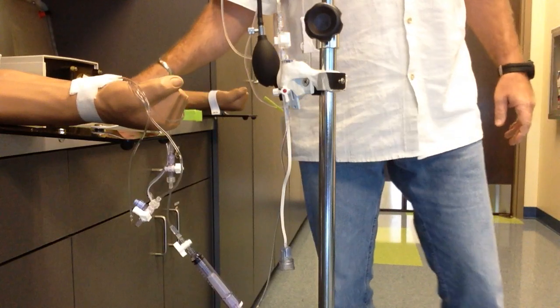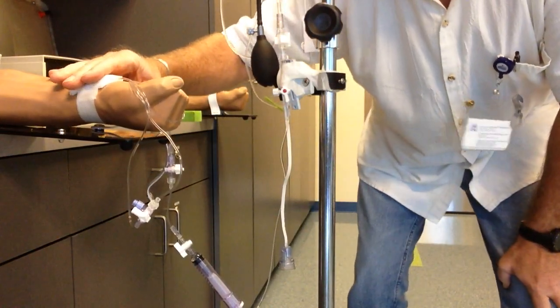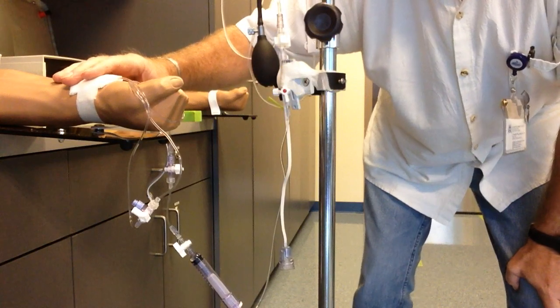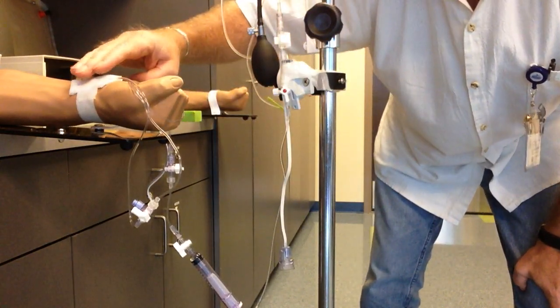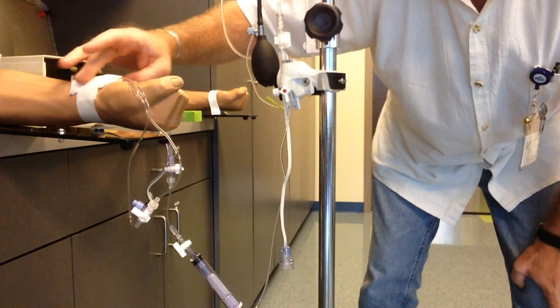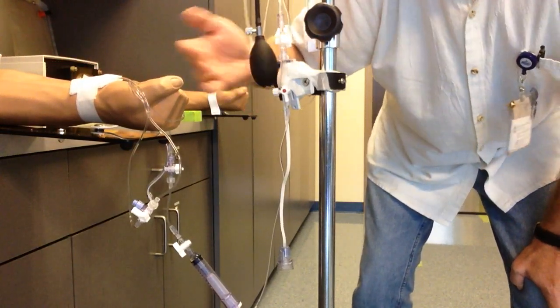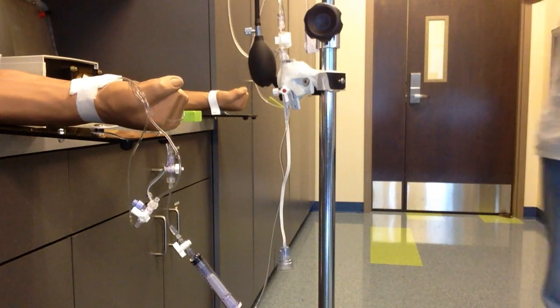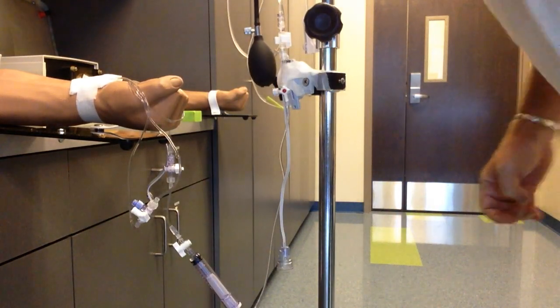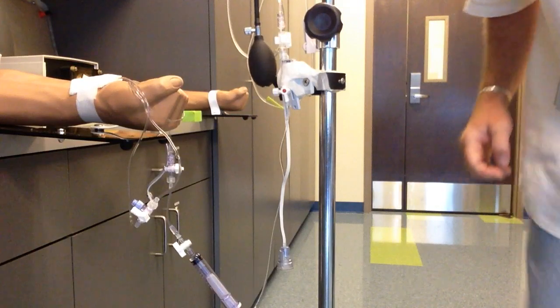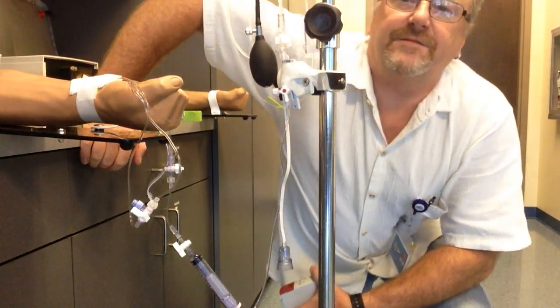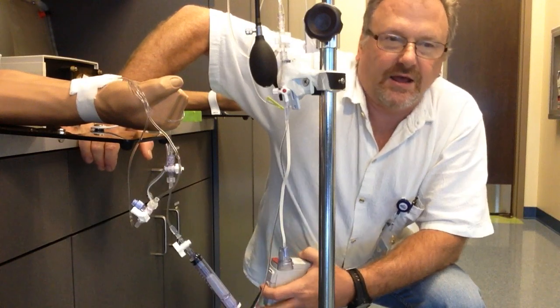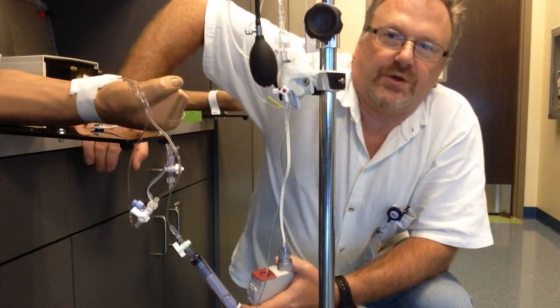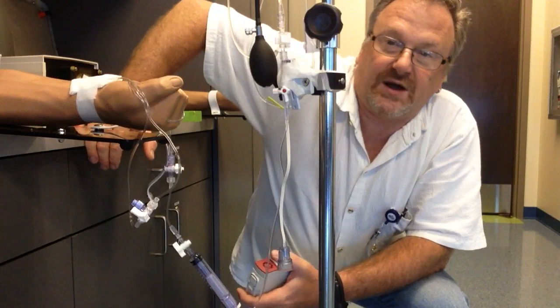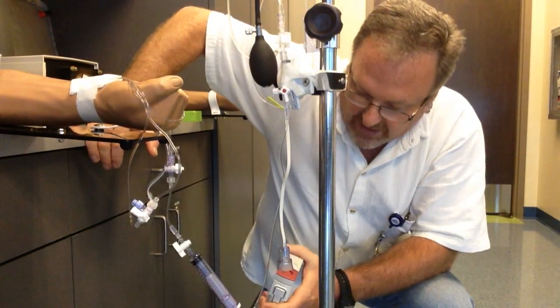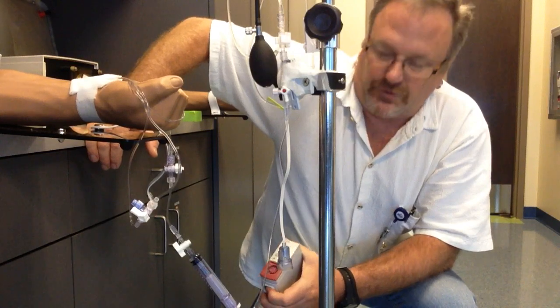So now my transducer and the reading spot for the blood pressure, this is invasive blood pressure monitoring, we can also use it to take blood samples, but where the pressure is being read and my transducer are at exactly the same level. What you do need to understand is how the level affects the pressures being read. If your transducer is too low, your blood pressure may read too high. If your transducer is too high, your blood pressure may read too low. And you also need to know the other things that will affect your pressure readings.